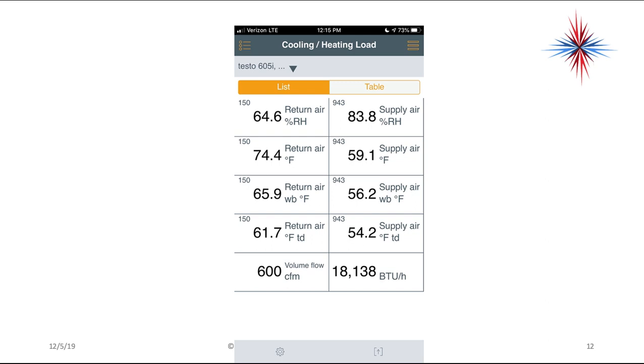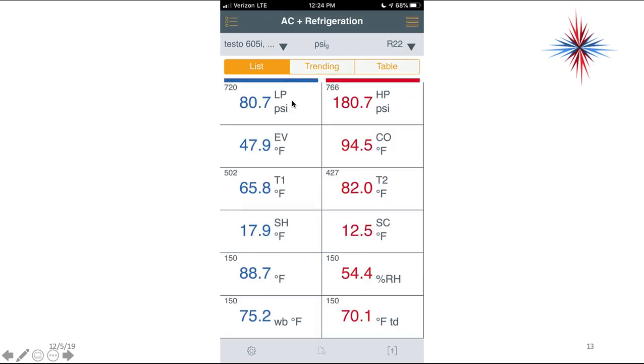Here's an example of the output of a digital psychrometer — the Testo smart probes. We had one in the return air and one in the supply air. It gives us the relative humidity for both, and it can also calculate temperature differences. For example, outside readings showed 88.7 degrees dry bulb, 75.2 wet bulb, and 54.4% relative humidity.